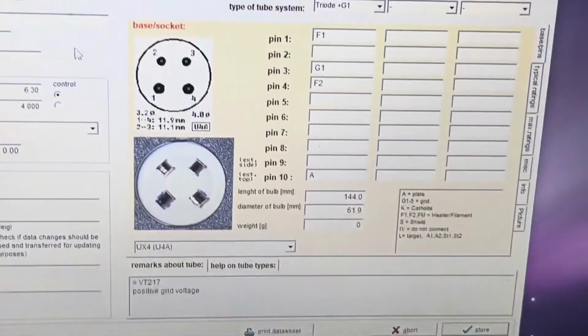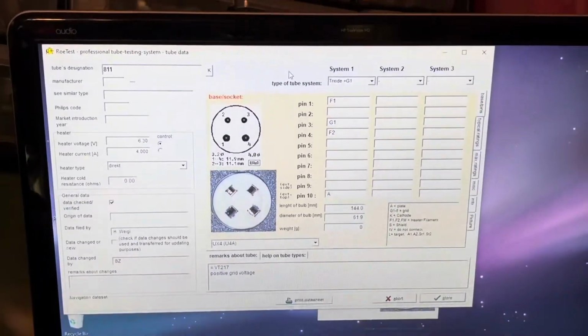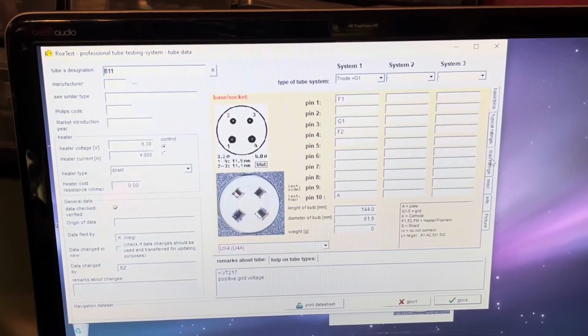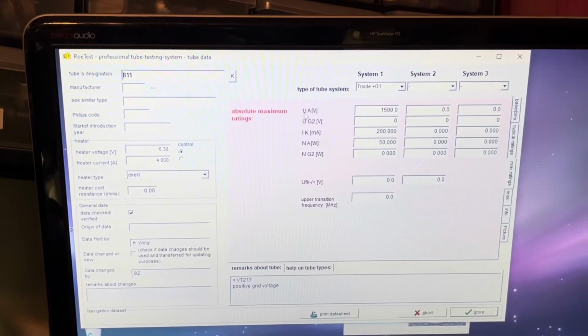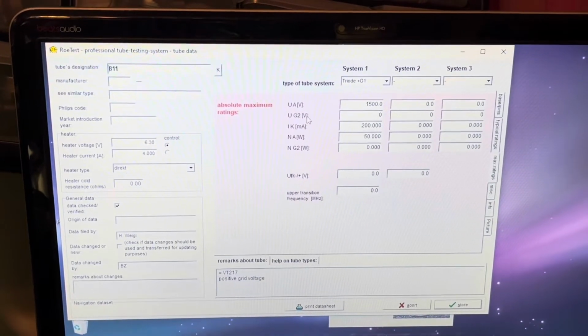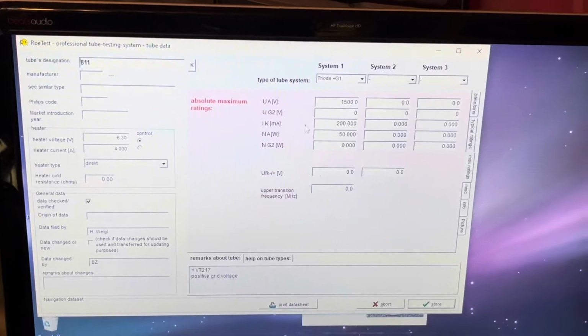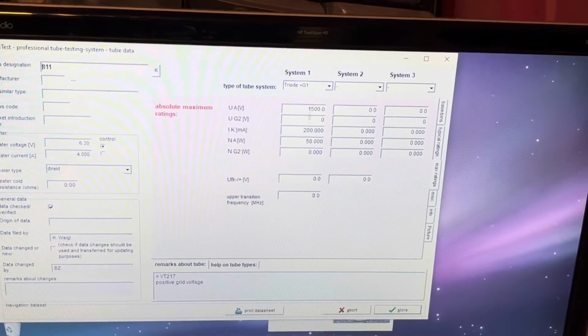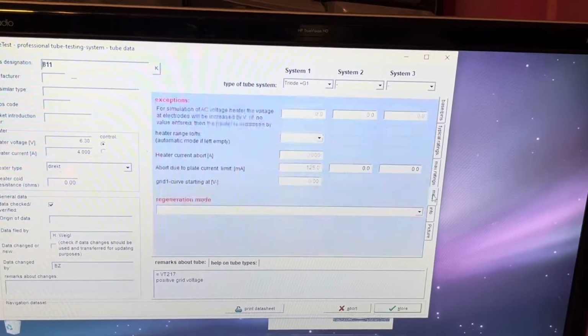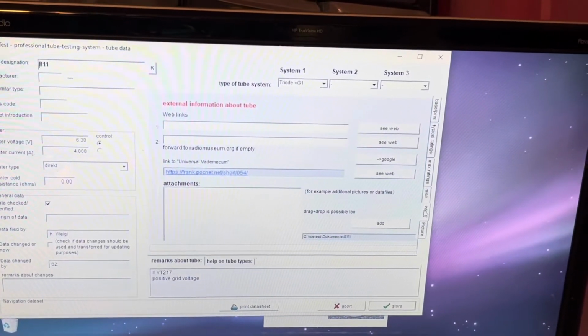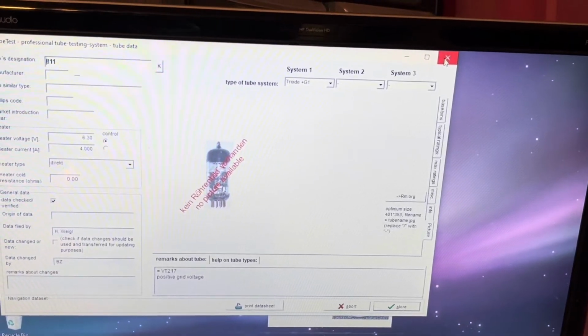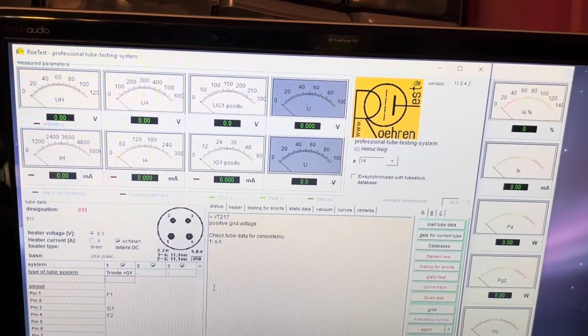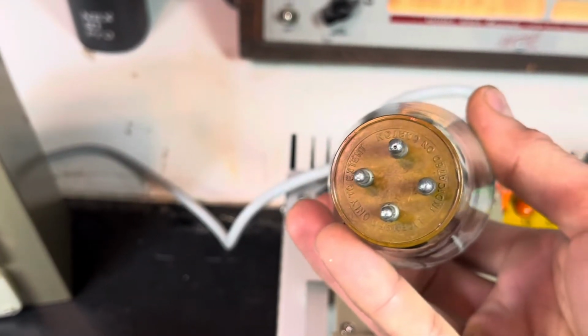Okay, keep in mind, you can come over here for any data that's already in the database and alter the parameters of the tube. So if you want to lower its maximum ratings, you can do so manually. Here it says voltage anode 1500. Obviously the RoeTest only goes up to 600, but this is just showing its ratings and what you want to test it at, and other info you can add. So I'm just going to close that because I'm not going to modify this, and get the tube started on here. So when you put the tube on the RoeTest, the two fat pins go right here.